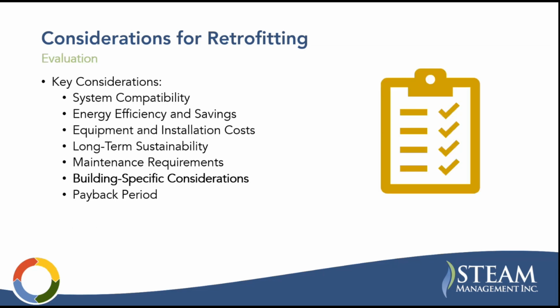So, key considerations for evaluation, which we'll go through in a little bit more detail. But generally speaking, you're looking at your system compatibility, how your distribution system is going to work with the new boilers, how your heat emitters can work with a lower operating temperature, things like that. Energy efficiency and savings, equipment and installation costs, long-term sustainability.